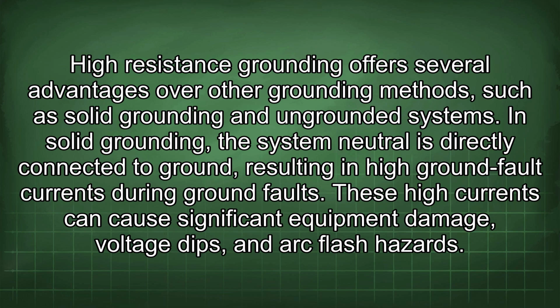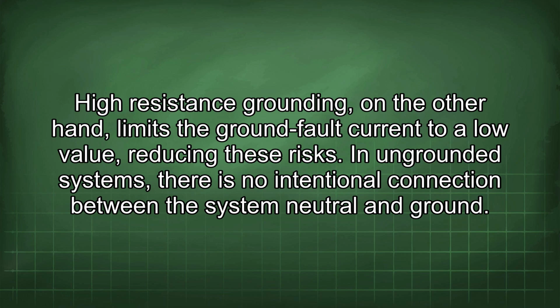In solid grounding, the system neutral is directly connected to ground, resulting in high ground fault currents during ground faults. These high currents can cause significant equipment damage, voltage dips, and arc flash hazards. High-resistance grounding, on the other hand, limits the ground fault current to a low value, reducing these risks.